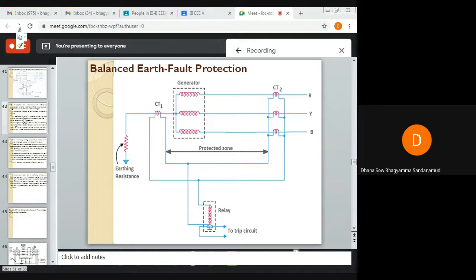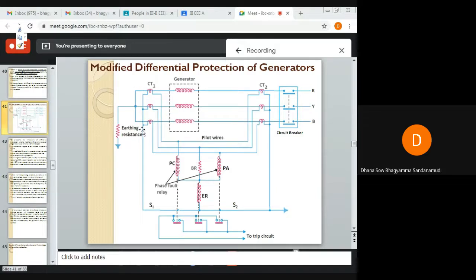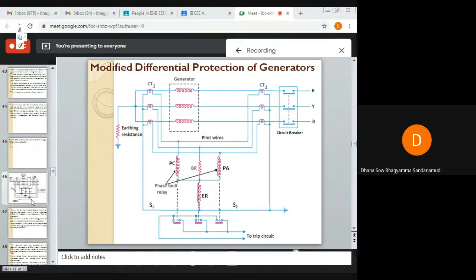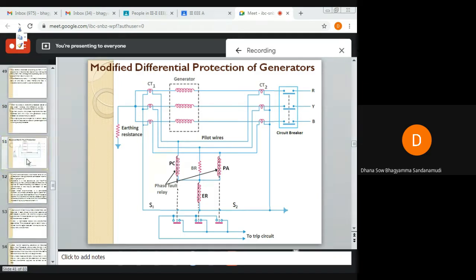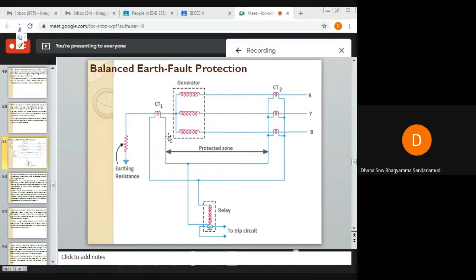You have just been shown the image. We have to accommodate the current transformers on each phase, on the neutral connection side. But if you see in this image, there is no space at all, no sufficient space to place the CTs. That is why Merz-Price protection cannot be used for small size alternators. So it is better to go for some other protection for small size alternators. That alternate protection method is balanced earth fault protection. Instead of Merz-Price circulating current protection, we can go for this other method, the balanced earth fault protection method.